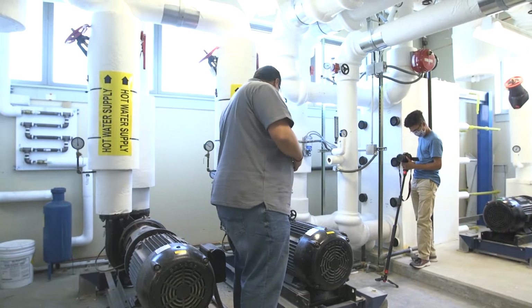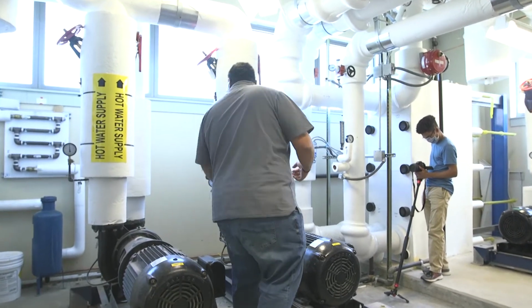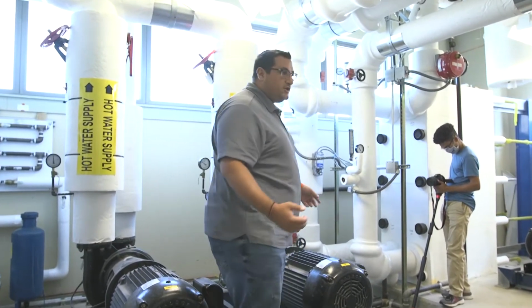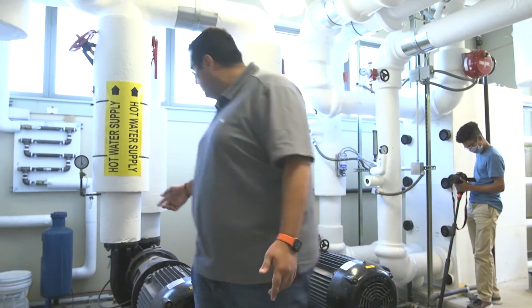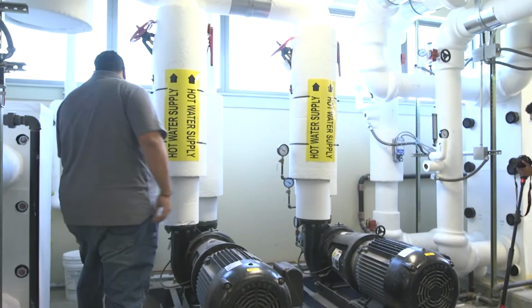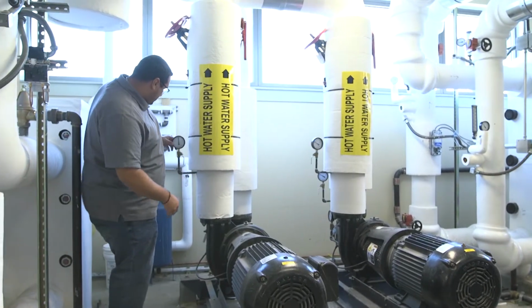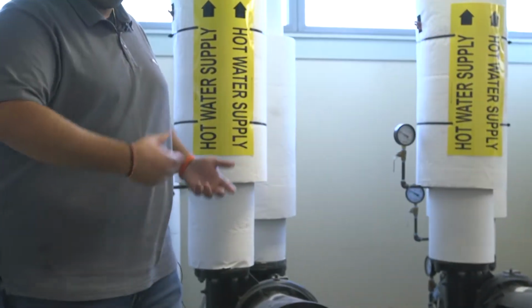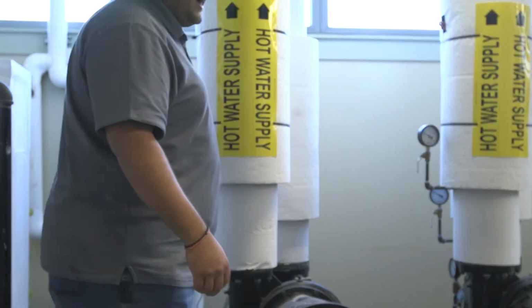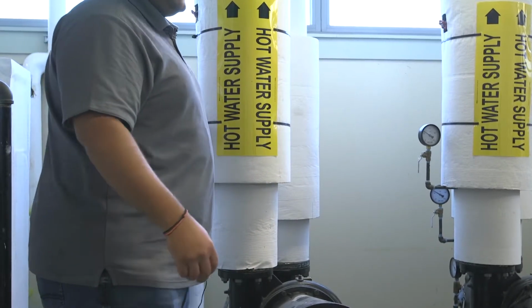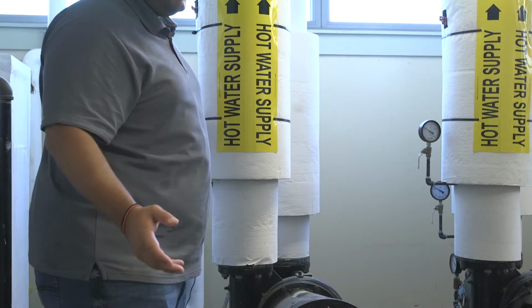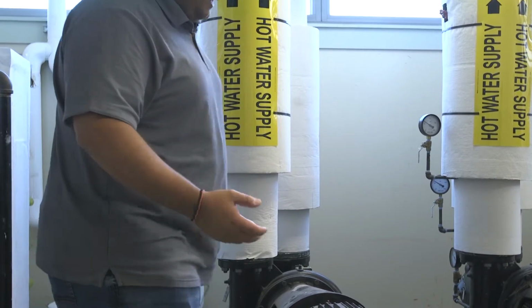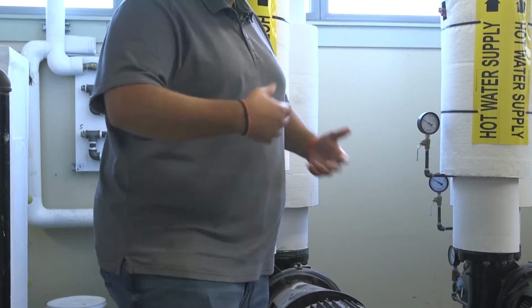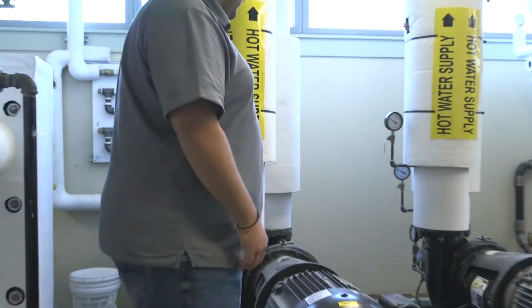So that's that. You should always check your suction and discharge pressures. Make sure that you're not having an issue. I think this pump's on right now. So you're sucking in at 52 psi, and you're discharging at 100 psi. Shows you it's working. If you see this gauge bouncing like crazy, that means you got air in your system more than likely, or the gauge is broken. But you should always check that as part of your maintenance and making sure that the pump is working correctly.